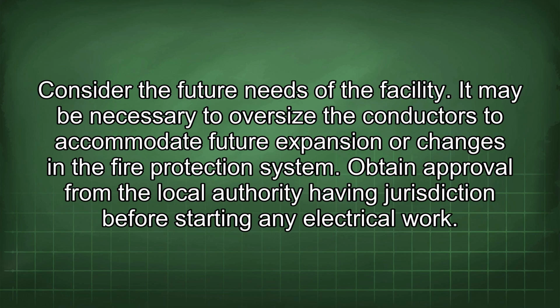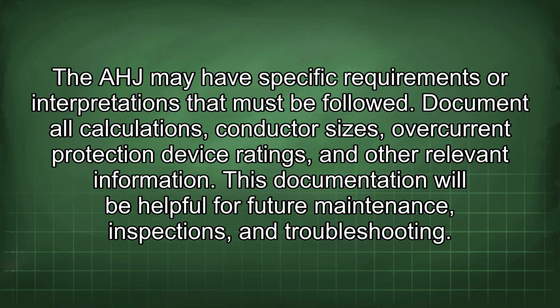Consider the future needs of the facility. It may be necessary to oversize the conductors to accommodate future expansion or changes in the fire protection system. Obtain approval from the local authority having jurisdiction before starting any electrical work. The AHJ may have specific requirements or interpretations that must be followed.